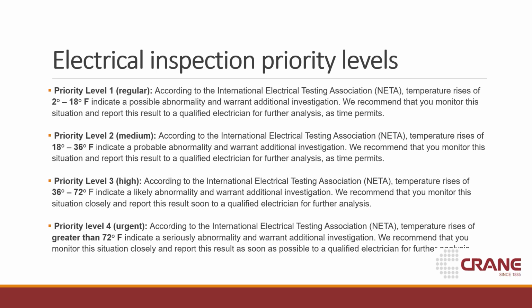If you're getting above 18 degrees above the ambient temperature—so if it was 72 degrees in here and we're looking at a breaker, and it's 92 degrees, that's a 20 degree difference—that's when we start looking at it as a higher priority level. That's something you should definitely follow up on by getting an electrician in there to check out the problem.